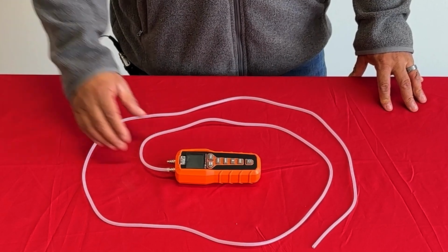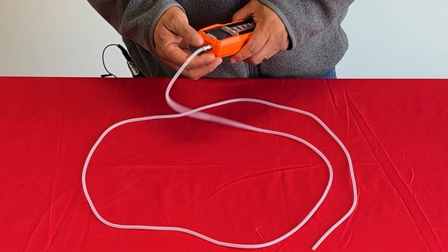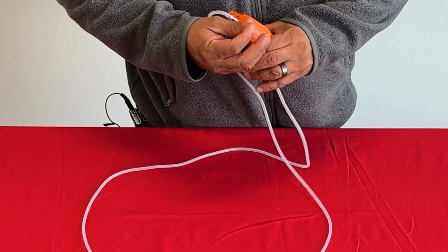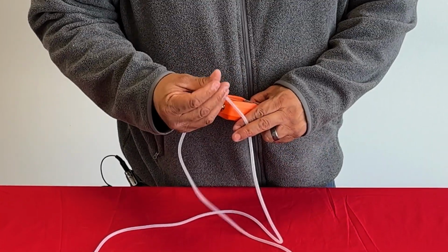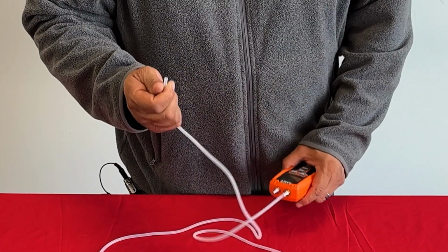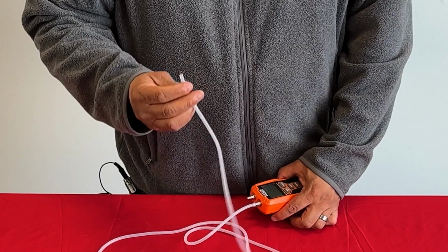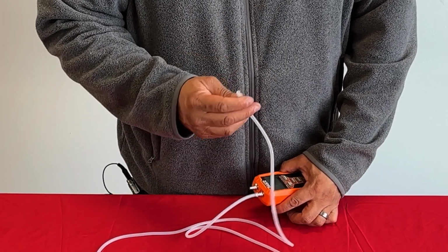The biggest tip I can give for using a manometer would be make sure that you have fittings to tap into the correct system. You're going to want multiple sizes. Some of your gas tubing is going to be 3/8, 1/4 inch, 3/16, just depending on what you're looking for. You want to make sure that you have multiple size fittings to get into the system and check proper gas pressure.